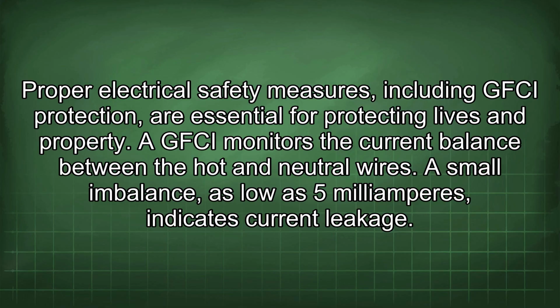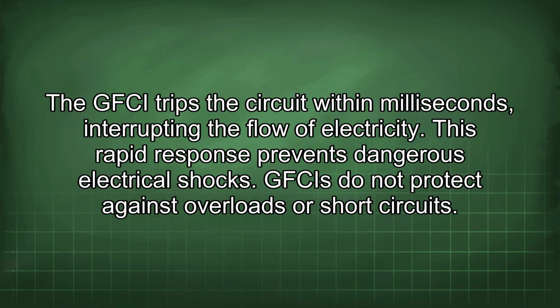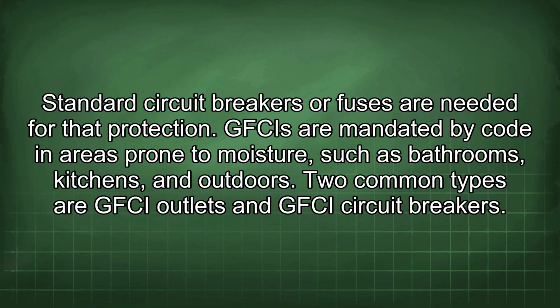A GFCI monitors the current balance between the hot and neutral wires. A small imbalance, as low as 5 mA, indicates current leakage. The GFCI trips the circuit within milliseconds, interrupting the flow of electricity. This rapid response prevents dangerous electrical shocks. GFCIs do not protect against overloads or short circuits. Standard circuit breakers or fuses are needed for that protection. GFCIs are mandated by code in areas prone to moisture, such as bathrooms, kitchens, and outdoors.